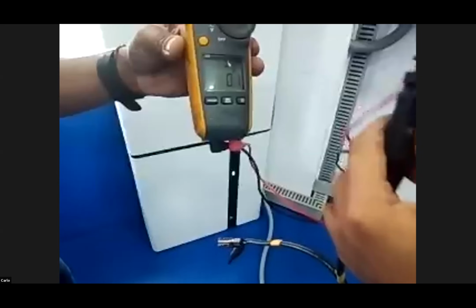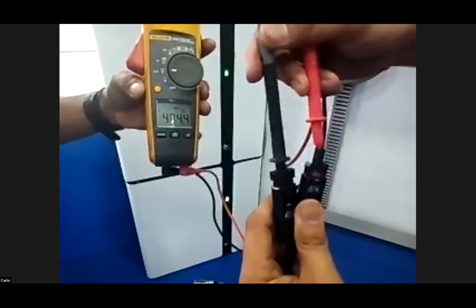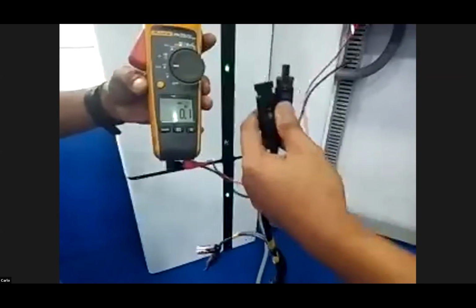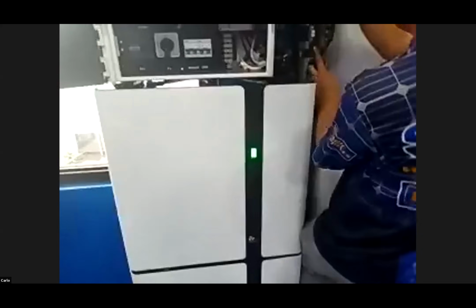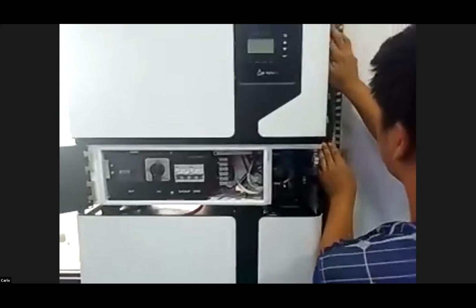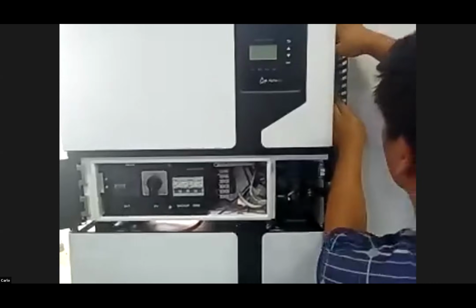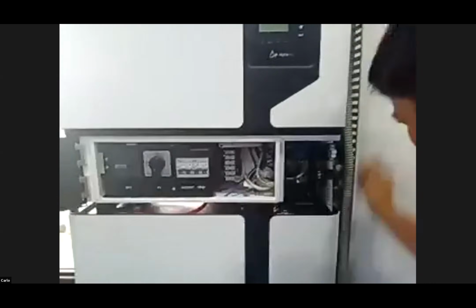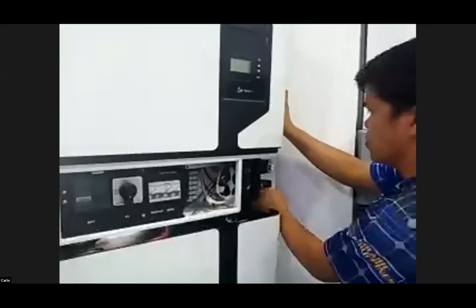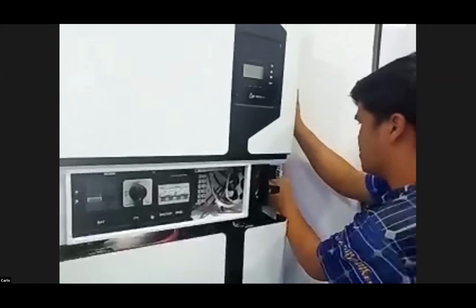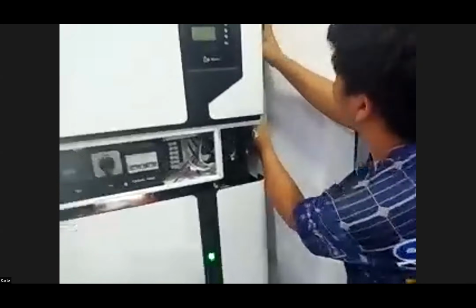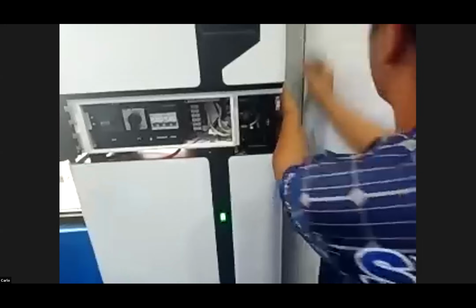Not for PV protection, right, Kevin? Yeah, you're right, Jed. For the MPPT, the SPD is already integrated inside, but the switch is just a manual break. So Kevin, is there a built-in SPD protection device or not? Yes, integrated inside for both DC and AC side. Fantastic - so yes, there is a built-in AC and DC SPD, so you can eliminate that from your requirement in your DC and AC combiner boxes. That's good savings too.